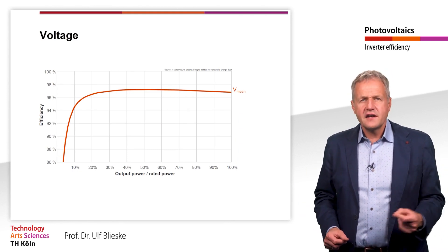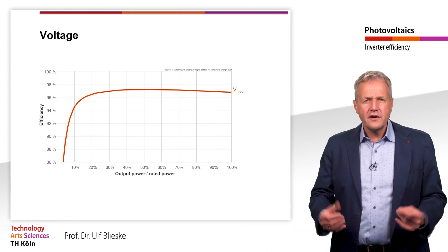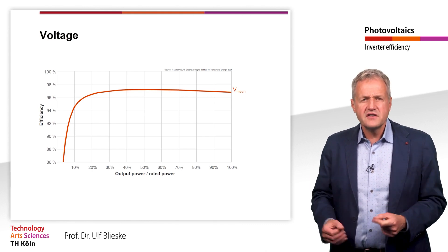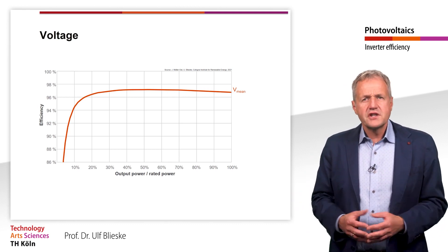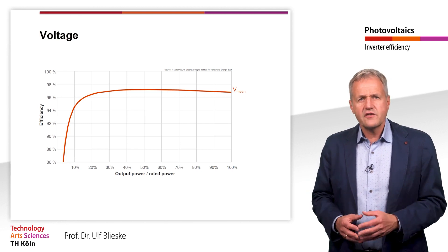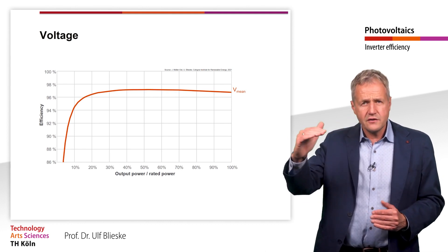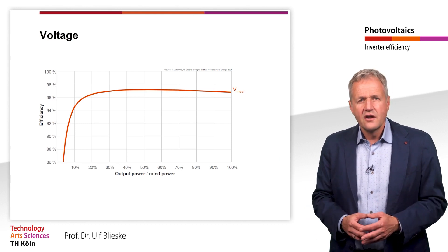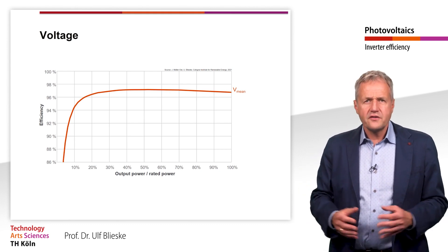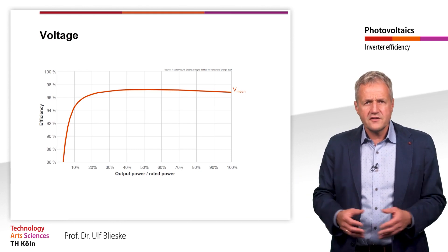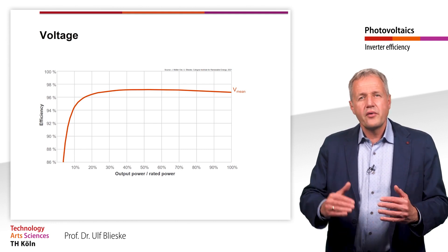A weighted efficiency therefore already says much more about the kind of average annual efficiency one can expect for a certain inverter. However, it must also be taken into account that the efficiency depends not only on the input power but also on the input voltage. The vast majority of inverters sold today are two-stage transformerless models. In the first stage, the input voltage of the PV generator is set to a certain voltage value and then converted to AC in the second stage. Conversion losses occur in both stages, and these losses also depend on the voltage.